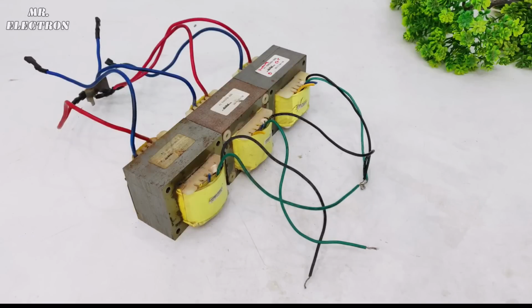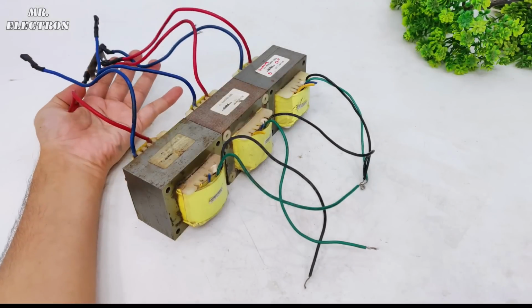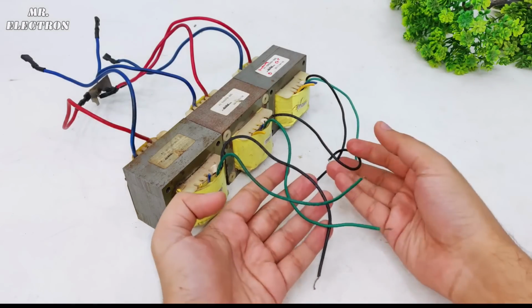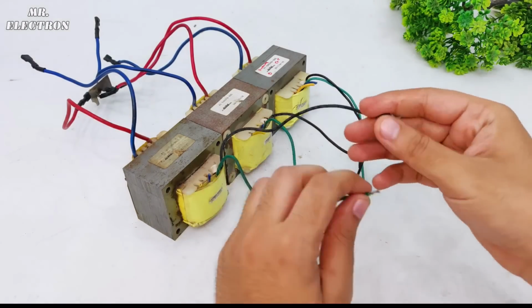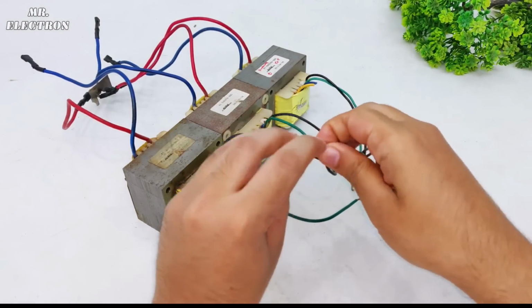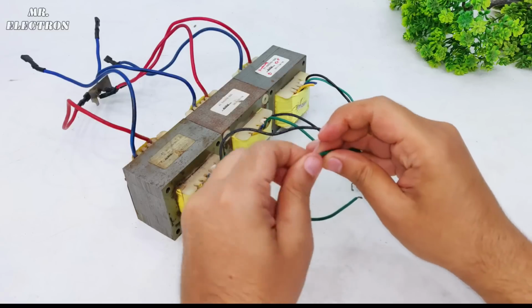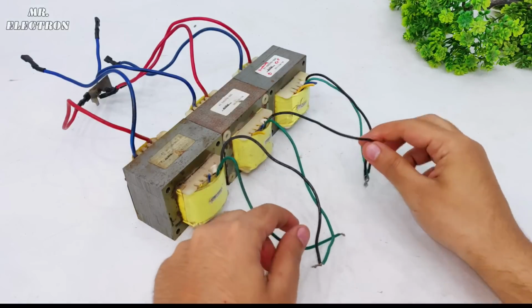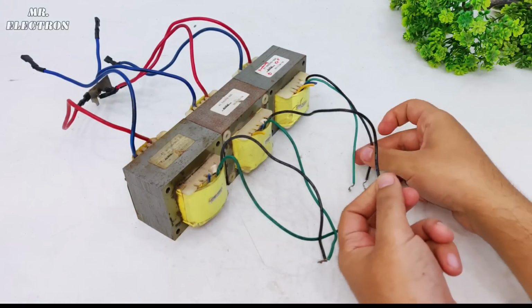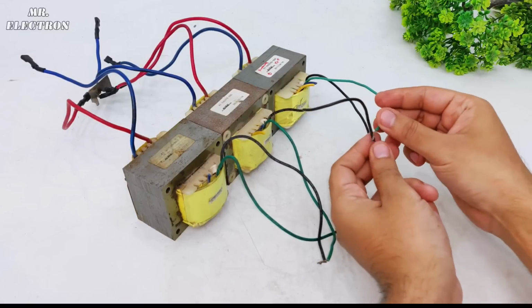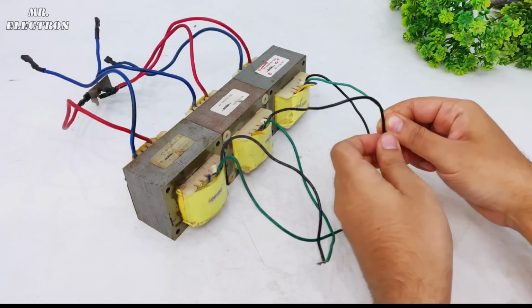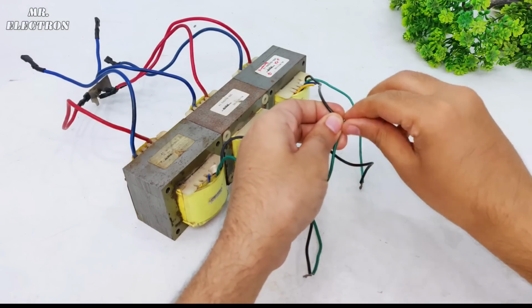Now for the last try, the secondary remains star connected, while for the primary high voltage side, I'm going to connect it to delta, for which the black wire of the first transformer will be connected to the green wire of the next transformer, and then the black wire of the next transformer will be connected to the green wire of the last transformer, and after that the remaining two wires.